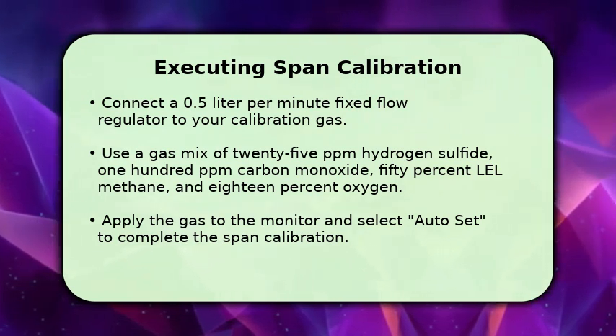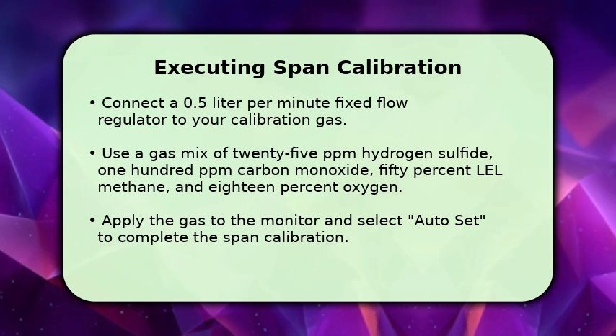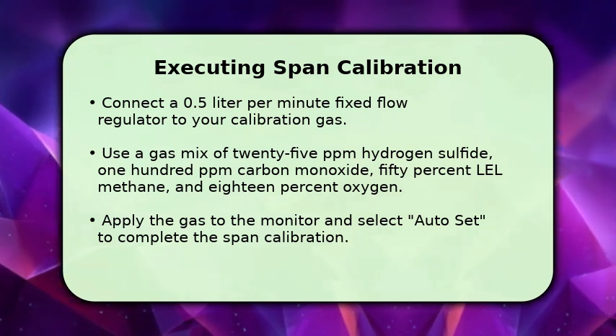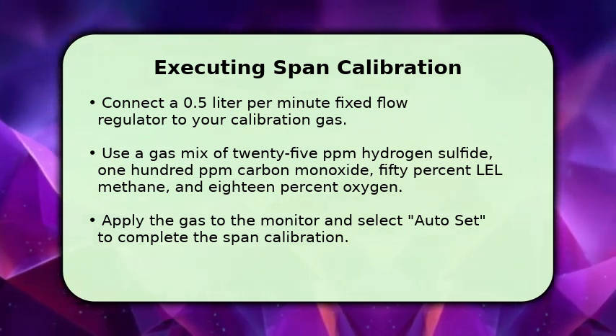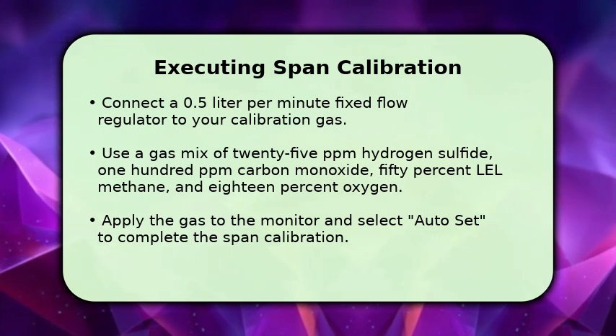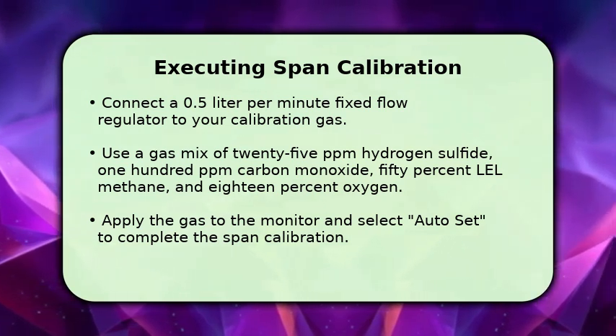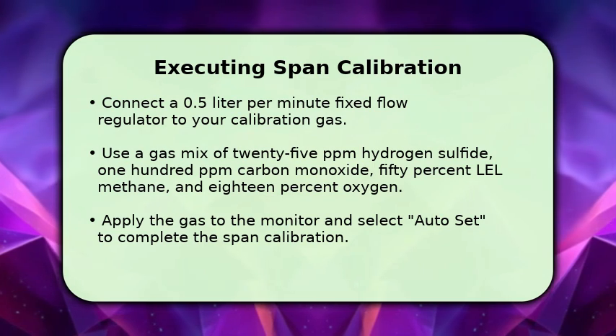Connect the gas to the monitor's inlet. Once the gas is flowing, select Auto set on the device to allow it to automatically adjust the sensor readings to the known gas concentrations, completing the span calibration.